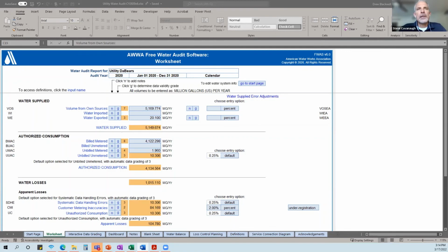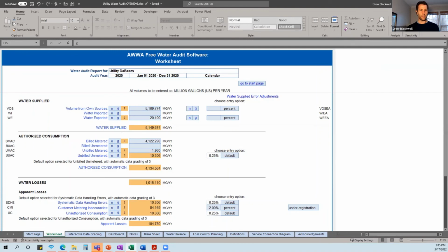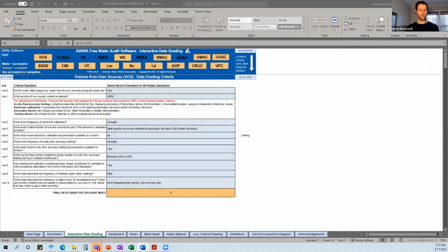Yeah, actually it's the electronic signal, and we do that annually. They're doing calibration between the meter and the SCADA. We also perform a quality check on the data that's recorded by the operator and the flows in the SCADA. Okay, great. That's helpful to understand that we're checking for any data transfer errors at the secondary and tertiary devices. I noticed there weren't any records of that in what you provided. Do you know if there's any documentation available for the records from those annual calibrations? I'm not sure. I've never seen it, if it is. Okay.